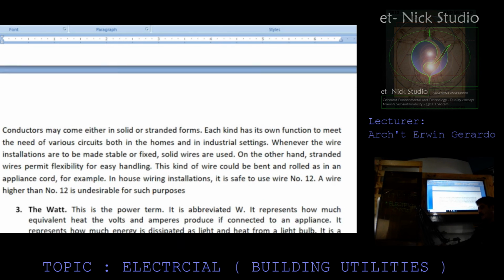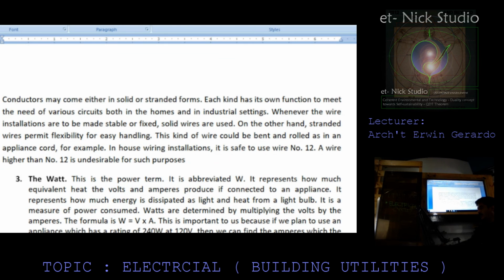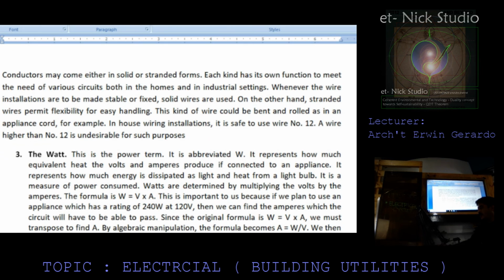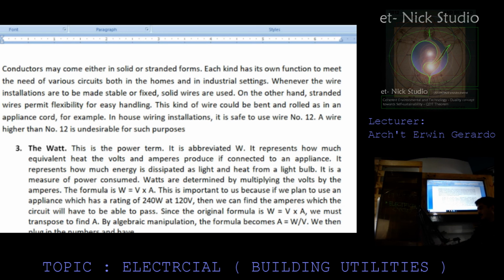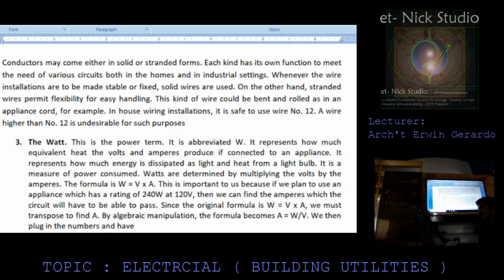Conductors may come either in solid or stranded form. Each kind has its own function to meet. For the needs of circuits both in homes and industrial settings, whenever the wire installation is to be stable or fixed, solid wires are used. On the other hand, stranded wires permit flexibility or easy handling. This kind of wire can be bent and rolled, as in an appliance cord. For example, in house wiring installation, it is safe to use number 12. A wire higher than number 12 is undesirable for such purpose.